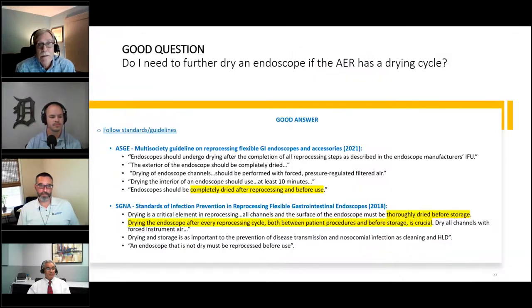Endoscope drying after processing has gained increased attention in recent years, both because of research and clinical investigations that have shown the real reality of residual moisture, especially for channeled endoscopes. It's not been uncommon during site visits to see scopes hanging in storage still wet on the outside, and not uncommonly dripping water onto the floor of the scope cabinet. We really need to change the mindset that these are red flags. Residual moisture allows an environment favorable to bacterial proliferation and biofilm development.